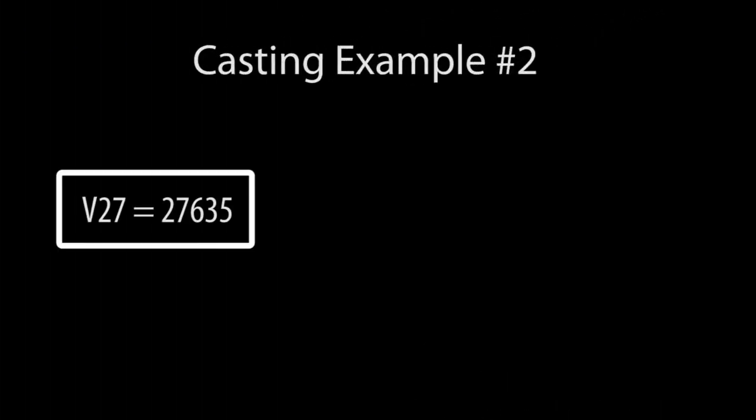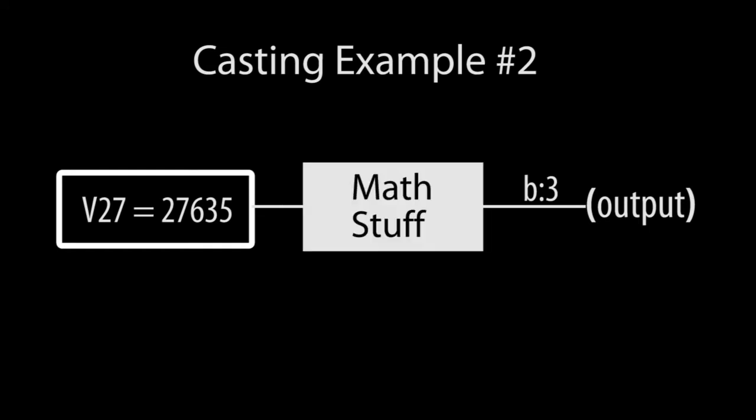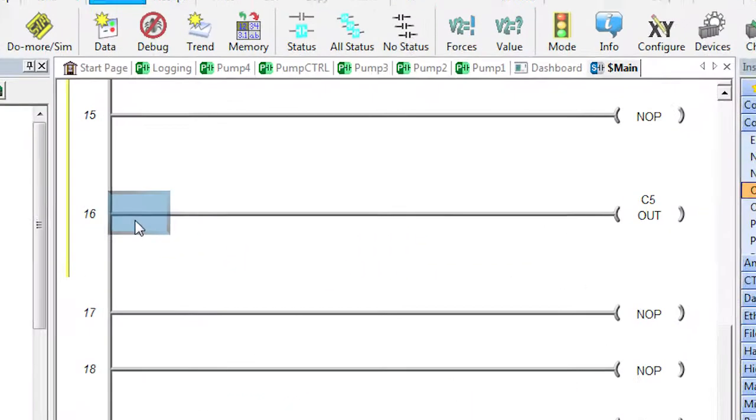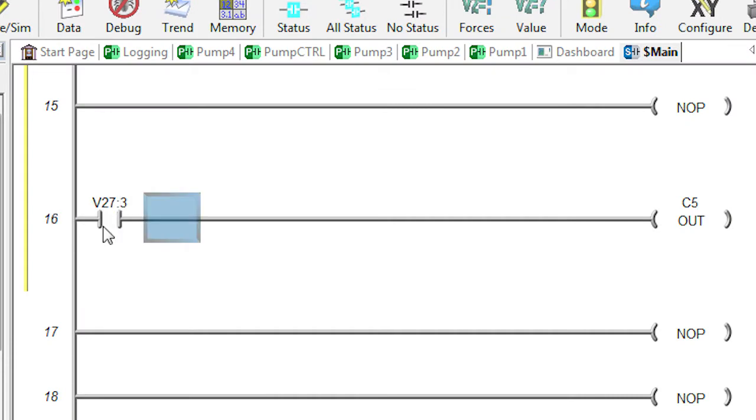Suppose you want to take one bit of an unsigned word and use that to drive an output coil. Again, you could do some math and masking and shifting, but why not do it the easy way? Simply tell Do-more you want the 4th bit, numbering starts at 0, to drive the output.